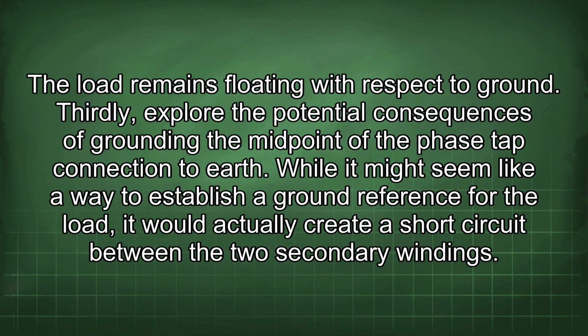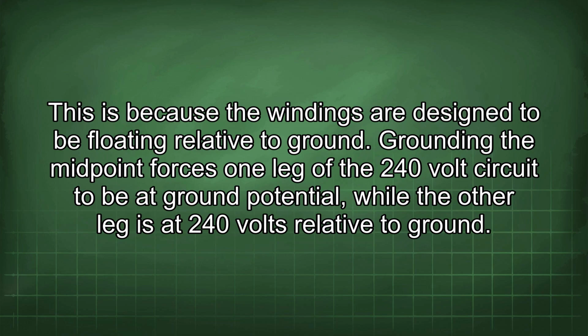Thirdly, explore the potential consequences of grounding the midpoint of the phase tap connection to earth. While it might seem like a way to establish a ground reference for the load, it would actually create a short circuit between the two secondary windings. This is because the windings are designed to be floating relative to ground. Grounding the midpoint forces one leg of the 240 volt circuit to be at ground potential, while the other leg is at 240 volts relative to ground.